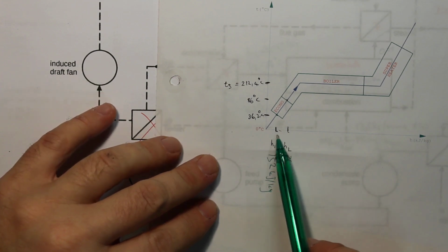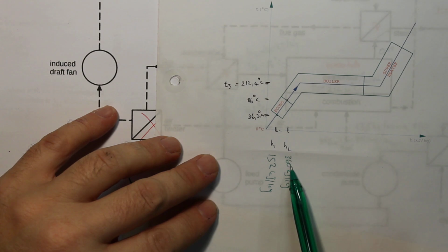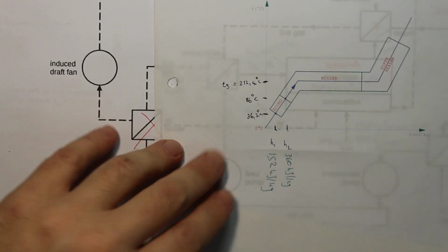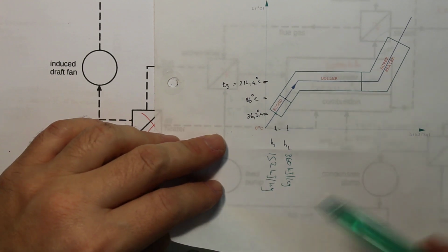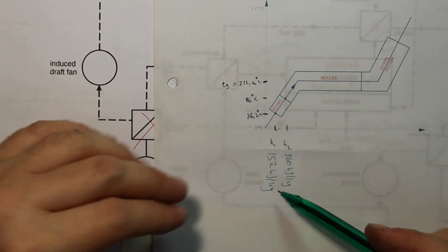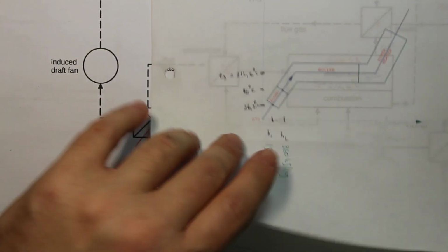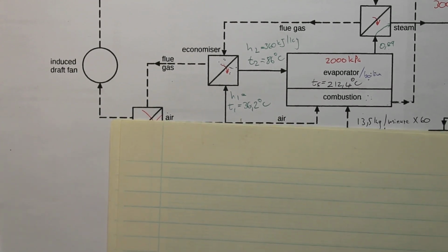So as the water went through the economizer, the heat applied to that water took it from 152 to 360. So how do we calculate it now? Because the enthalpy value is in kilojoules, heat energy per kilogram, and we didn't send 1 kilogram of water through, we sent more than that. So this is the formula to calculate it.